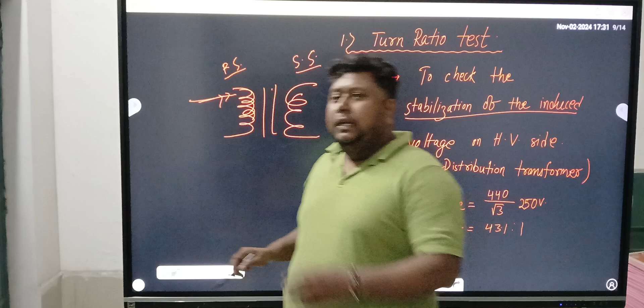Now the question is, is the induced voltage in the secondary in a proper ratio or not? That is the main thing we have to test. Because for example, if some of the windings are short circuited on the secondary side, or if there is a faulty condition in the core of the transformer at the secondary side, or if there is a turn-to-turn short circuit inside, any fault can result in a serious issue. Serious issue means if you are giving the supply to the primary side with that same ratio, there will be no induction of voltage on the secondary side as we require. So that is also a faulty condition of the transformer.